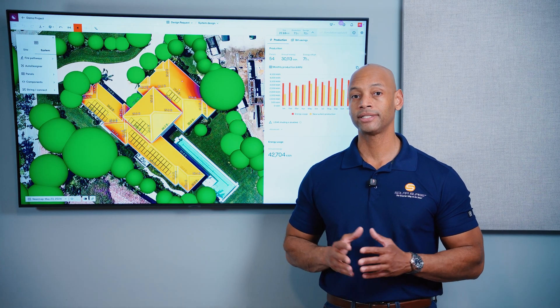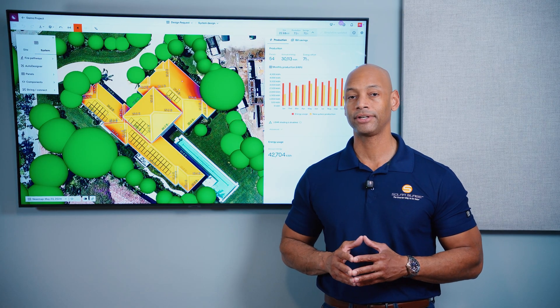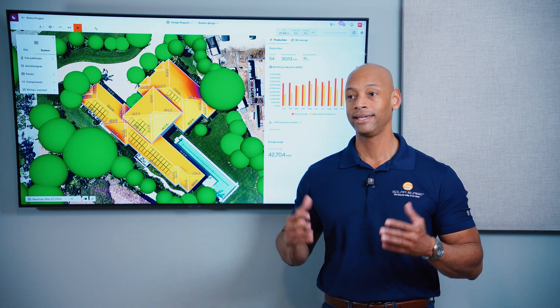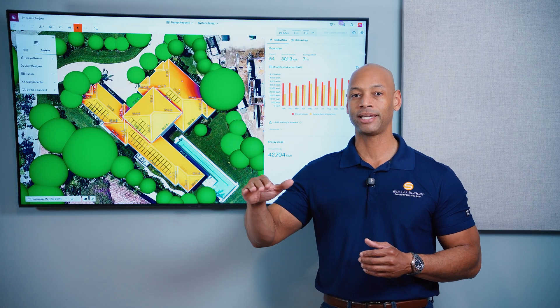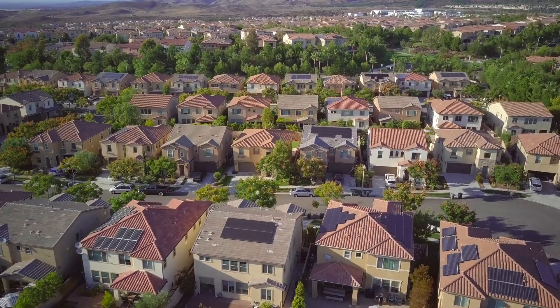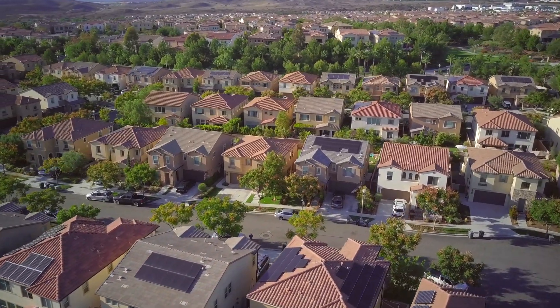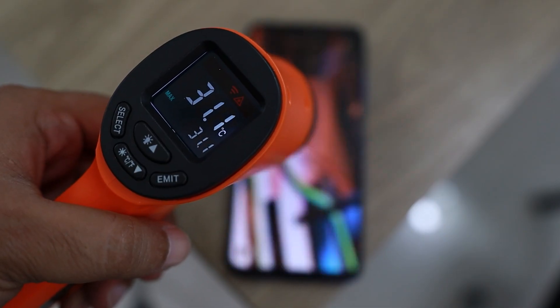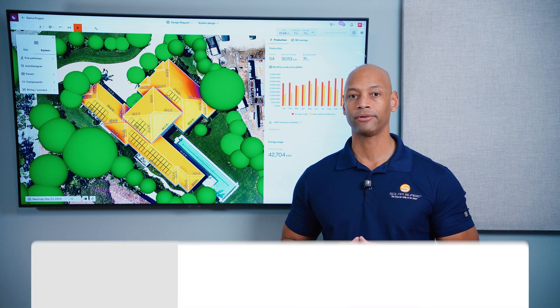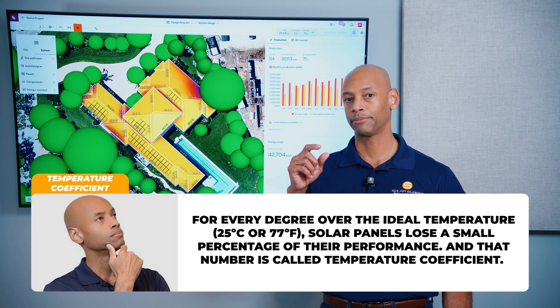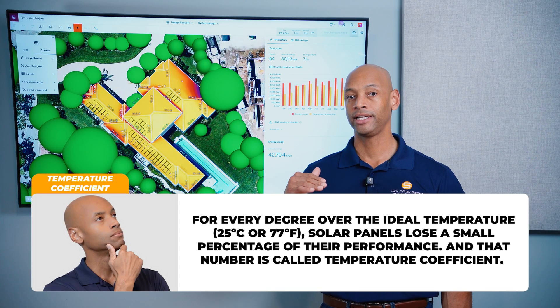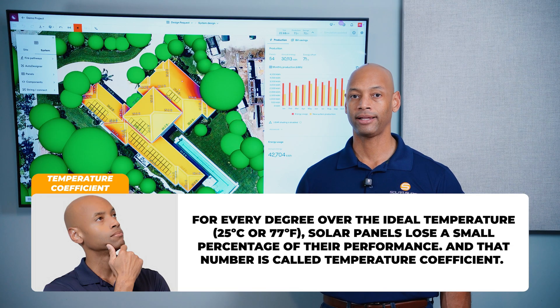A big part of those real-world conditions is ambient temperature. Standard test conditions use 77 degrees Fahrenheit or 25 degrees Celsius — basically a comfortable room temperature. However, in the real world, especially with rooftop solar, you could be dealing with extreme high temperatures — 130, 140, even 150 degrees or higher during the middle of summer. Solar panels, just like a lot of electrical equipment, lose efficiency and performance when operating at extreme heat. In the solar panel world we call this the temperature coefficient — the percentage of power output lost for each degree Celsius above the ideal operating temperature.